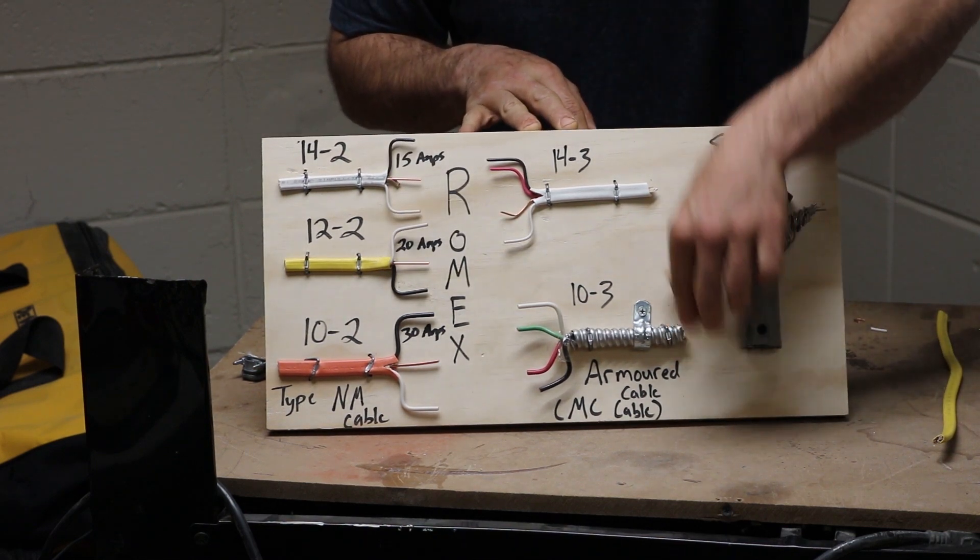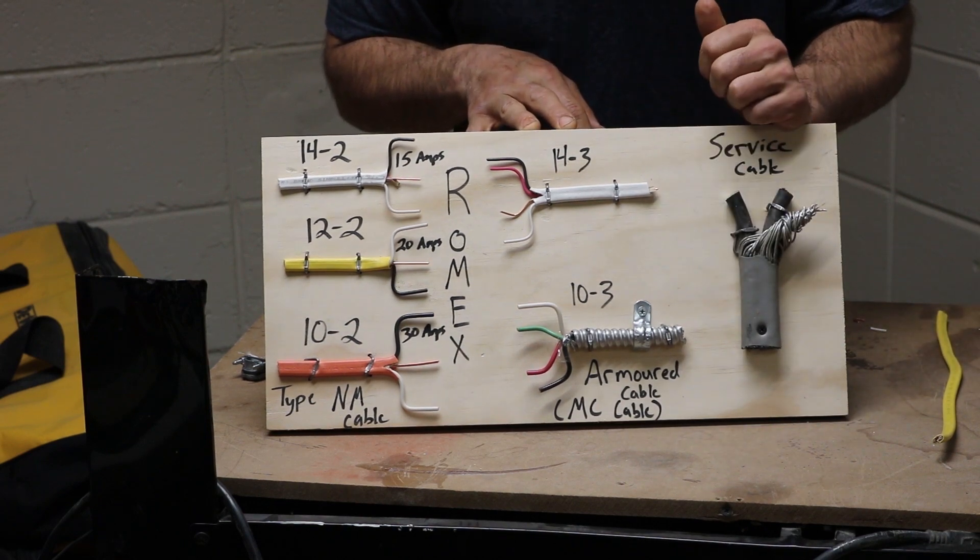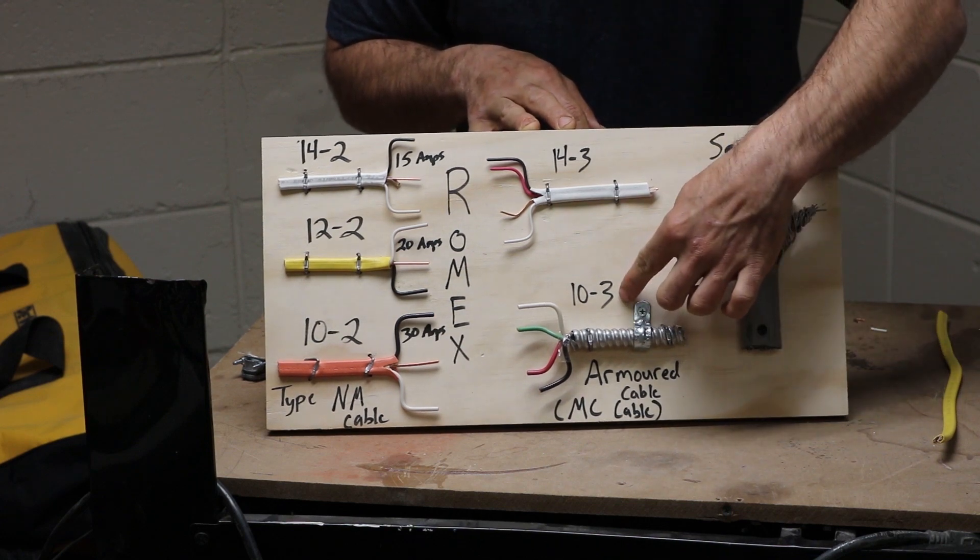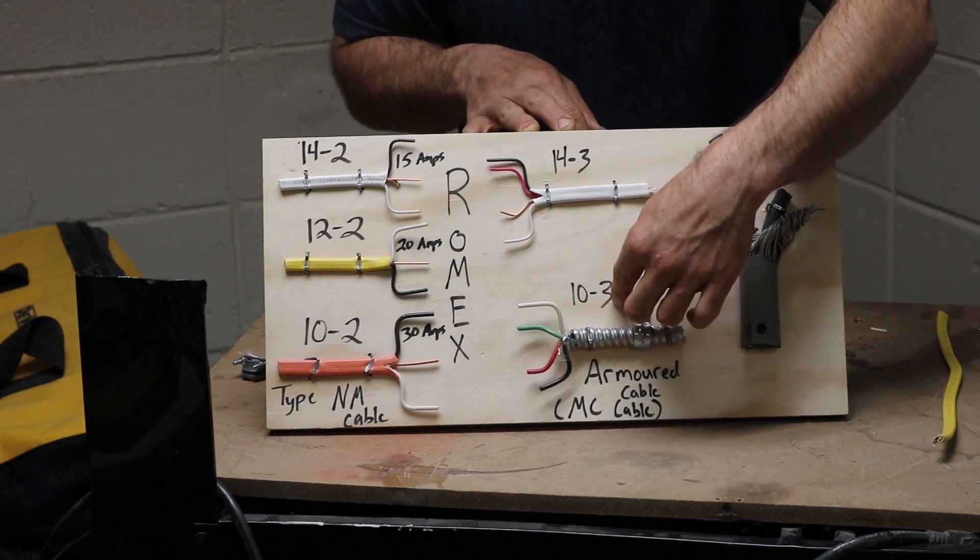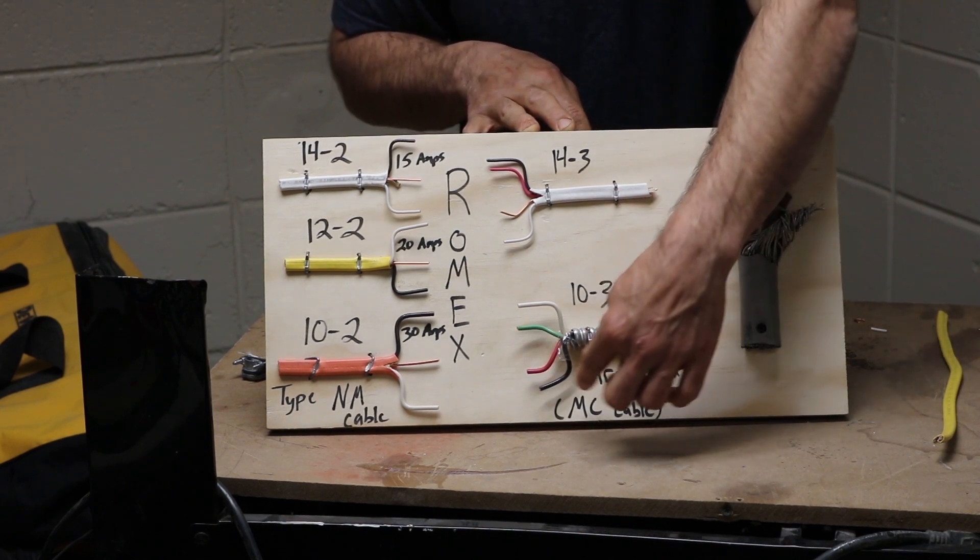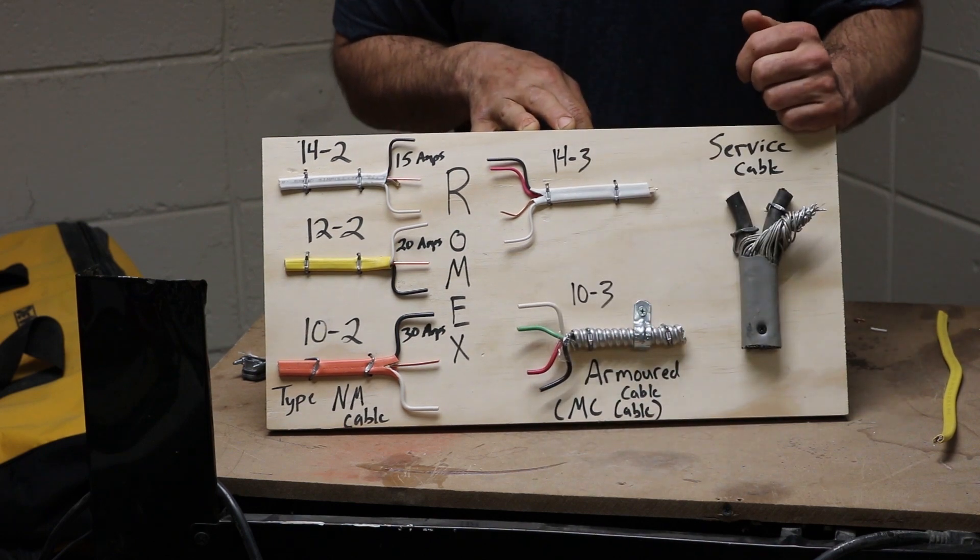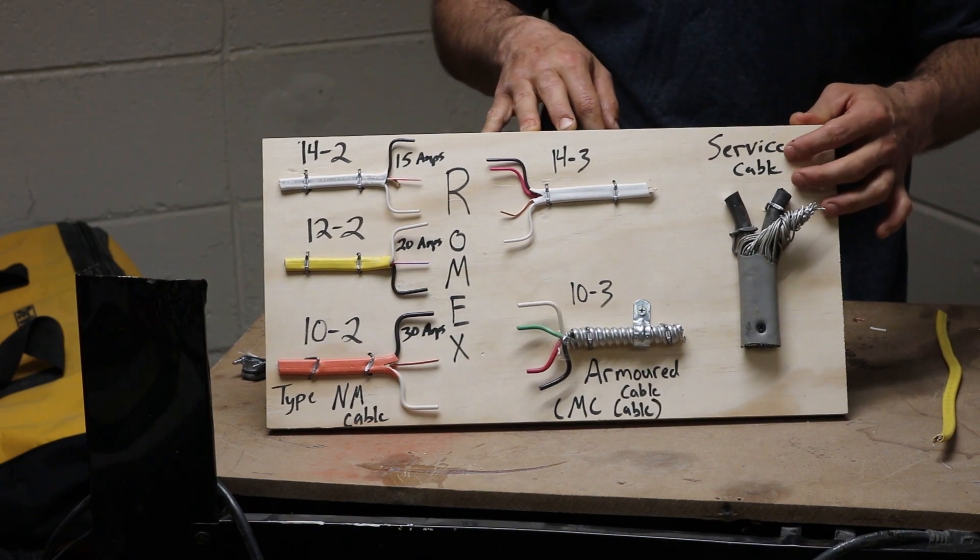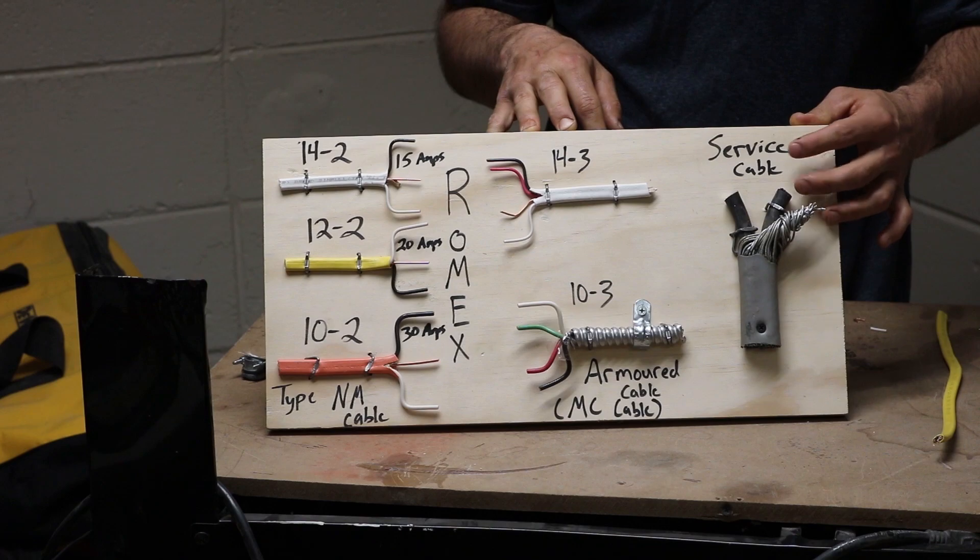This right here, NEC is going to call it armored cable. Trade name out in the field, you're going to call it MC cable. This would be an example of 10-3. Most commonly you'd be running 12-2 to 12-3, but I had a piece of scrap 10-3 laying around. As you can see, it's going to be black, red, white, and then your ground. You also have a service entry cable, and this service cable would be installed into a meter or a panel.